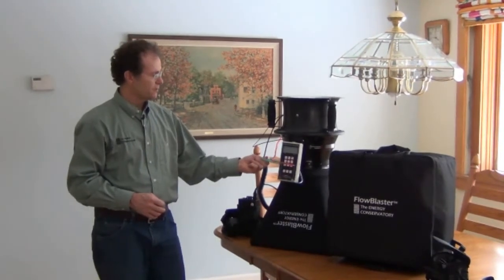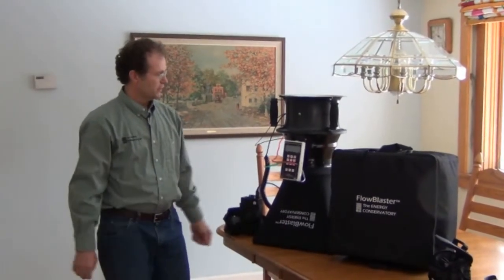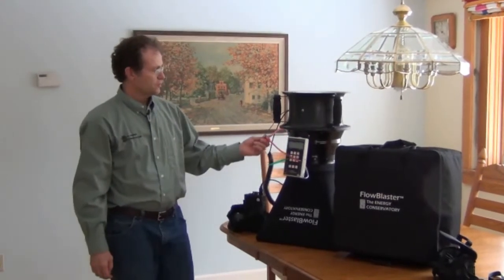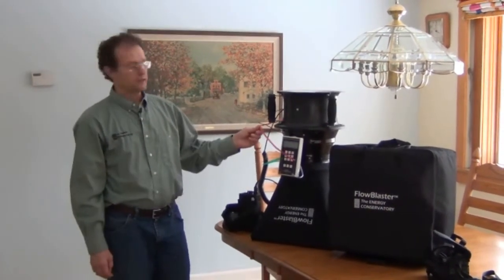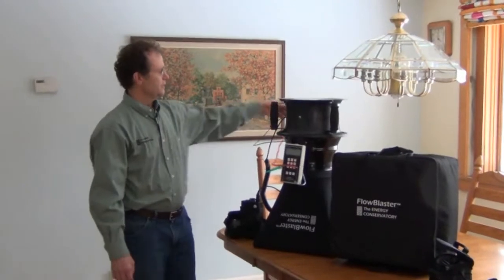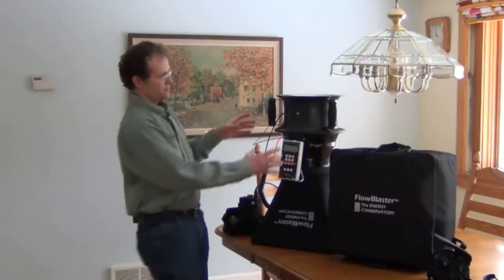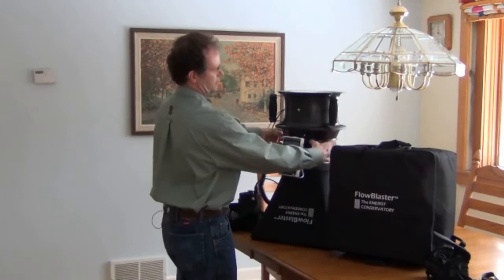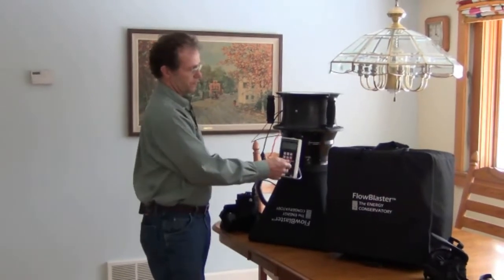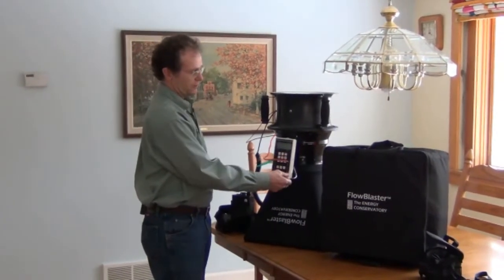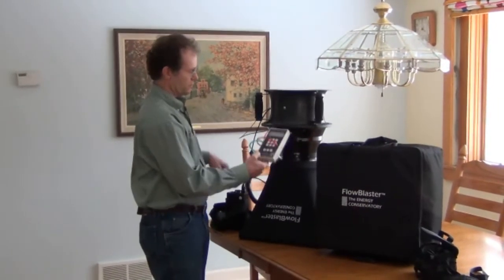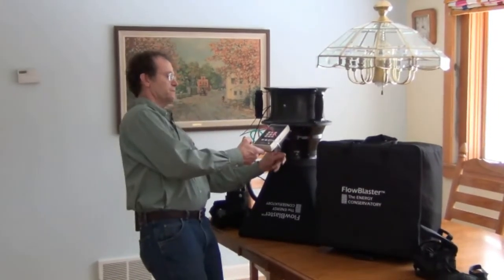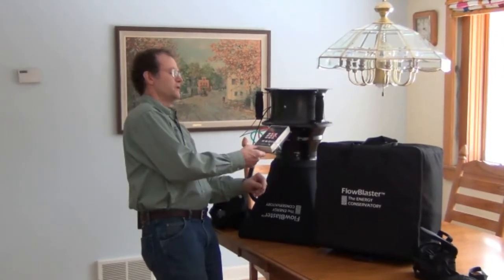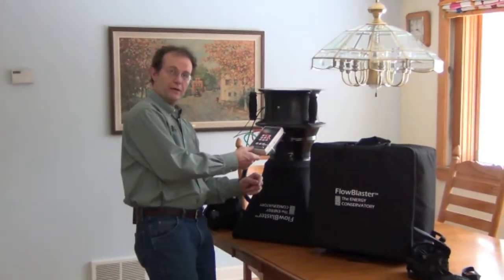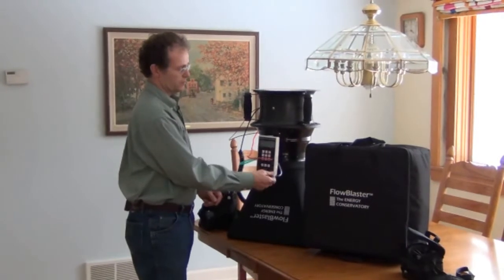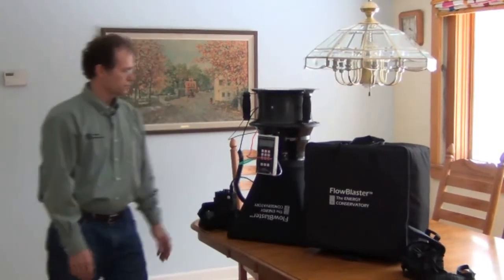So we've got our supply hose, input on channel A, input on channel B goes to the Duct Blaster fan, like when you're doing a normal Duct Blaster fan connection. And because the flow sensor on the fan is inside the housing here, our Duct Blaster fan pressure needs to reference that space in between. So there's a tap right up here that's labeled supply reference. So we're measuring supplies, so we need that clear reference hose on here.